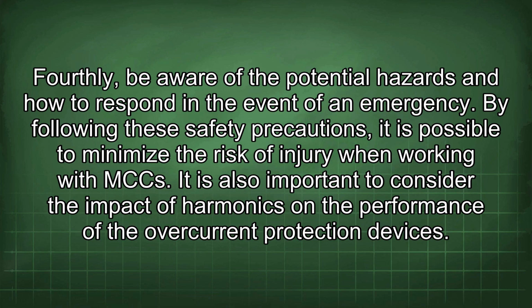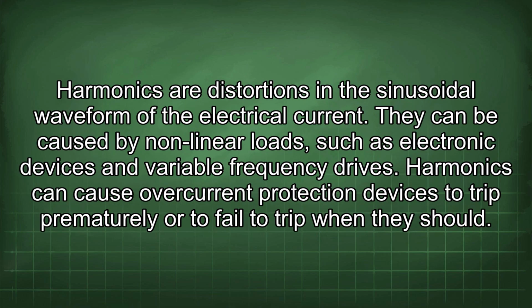By following these safety precautions, it is possible to minimize the risk of injury when working with MCC. It is also important to consider the impact of harmonics on the performance of the overcurrent protection devices. Harmonics are distortions in the sinusoidal waveform of the electrical current. They can be caused by nonlinear loads such as electronic devices and variable frequency drives. Harmonics can cause overcurrent protection devices to trip prematurely or to fail to trip when they should.